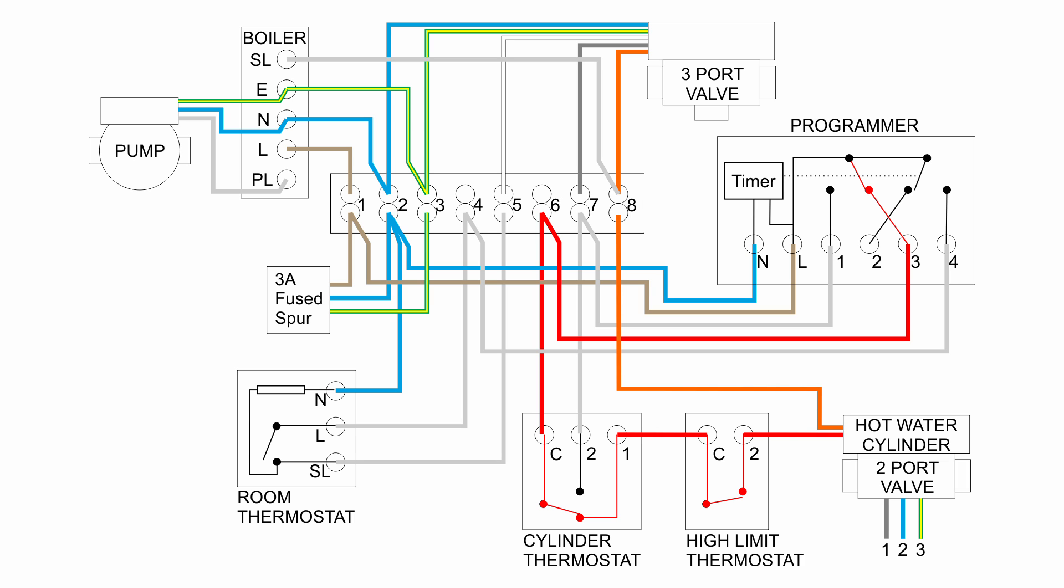And then that goes into the two port valve. This will activate the valve motor and open the valve. And then when the valve has actually opened, a switch inside the valve will then connect the orange wire coming out of there to the live input. And that's what goes back to terminal 8 in the wiring centre and turns on the boiler, just as we had previously.